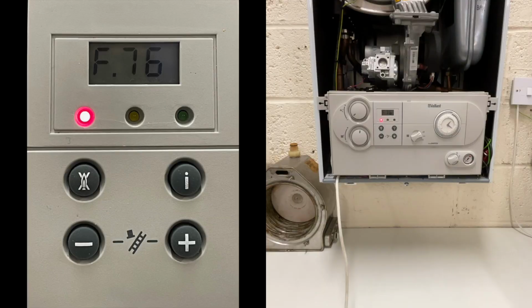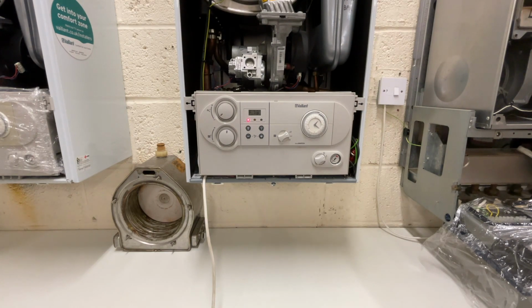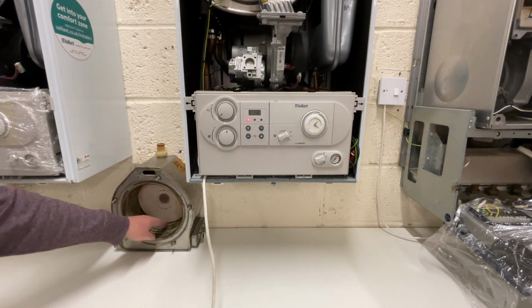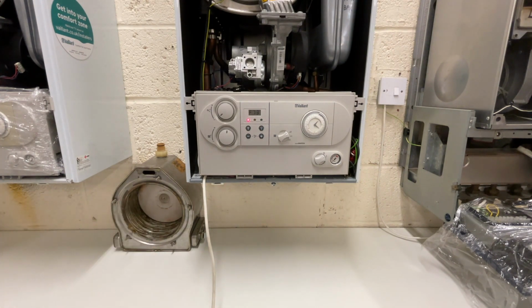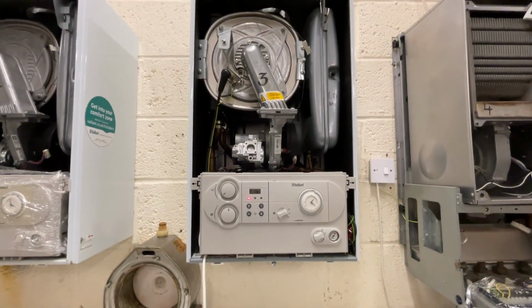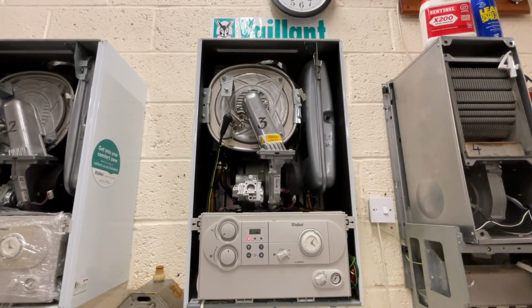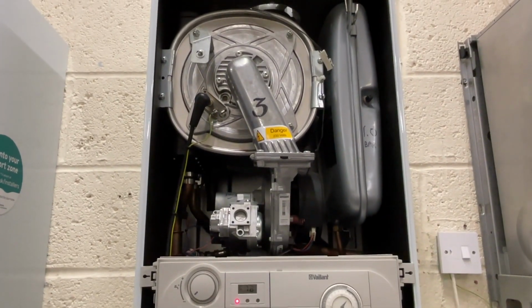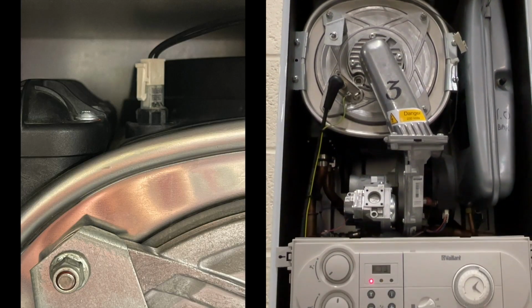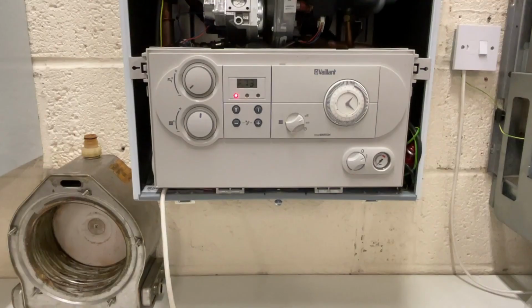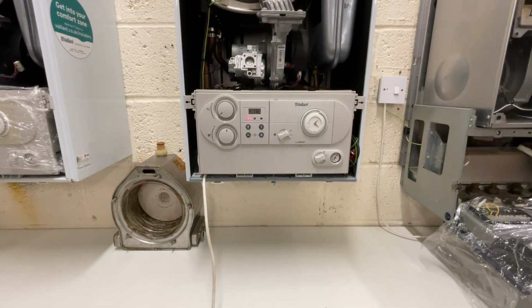If we look at 76, that is the worst one. That really means we need a new boiler. And that's telling us that all these highly efficient pipes, all of these inside, are blocked. And the boiler has reached very high temperatures, possibly around 100 or even higher, in a short space of time. And to protect itself, the fuse is blown. And there is a fuse. If you look at the top of the boiler, you'll see here, there's a white plug and a black lead, and it goes all the way to the top of the machine, and it's there as an overheat. And if it fails, the fuse blows.